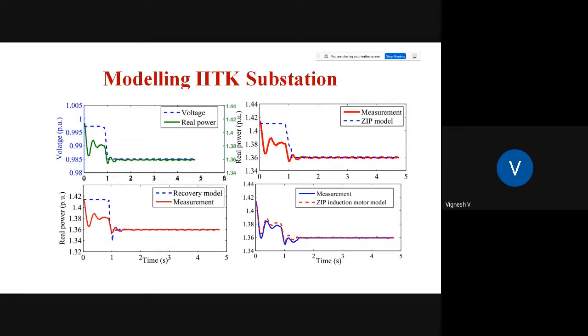In this case, we have an error between the measurements and the model output, because the actual load, that is, the aggregated load of the IIT Kanpur campus, is not just the induction motor. There could have been other types of loads, so we could not capture those dynamics. So it was only an approximation. But nevertheless, the ZIP induction motor model was able to almost match the dynamics, but not to the complete extent, because some of the dynamics could be of higher order, which is not being captured by the ZIP induction motor model. Yeah, next slide, please.